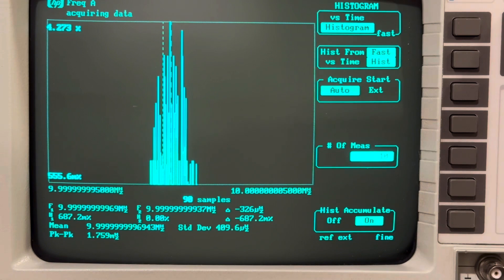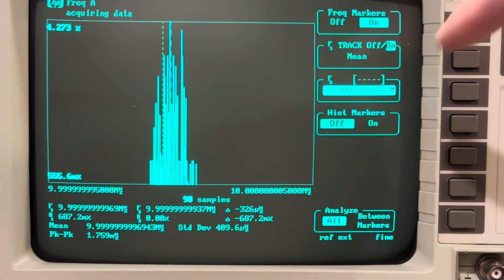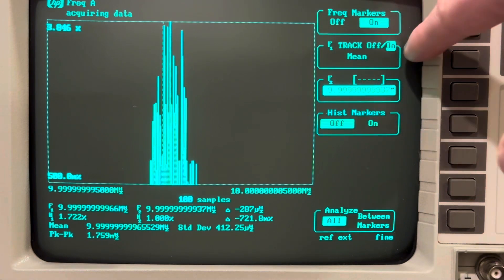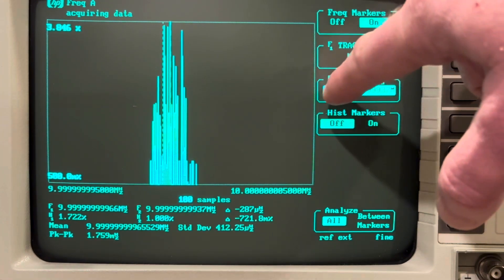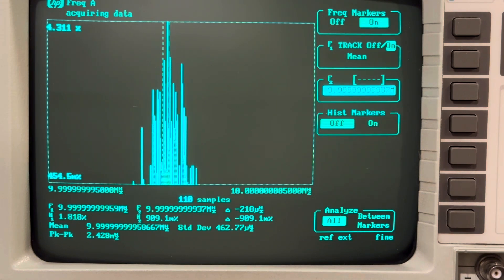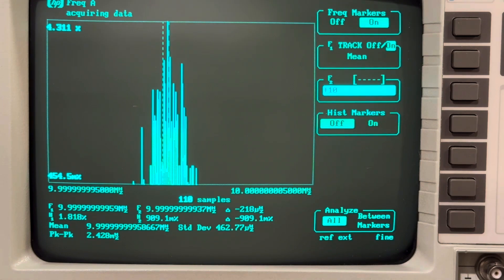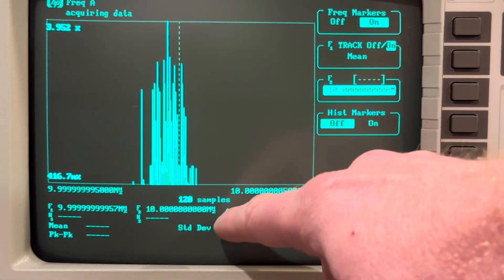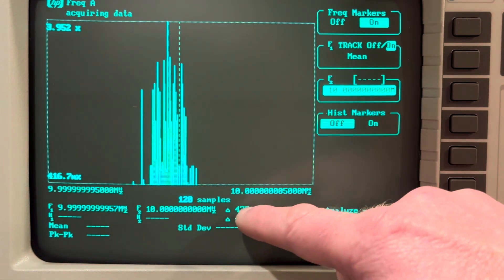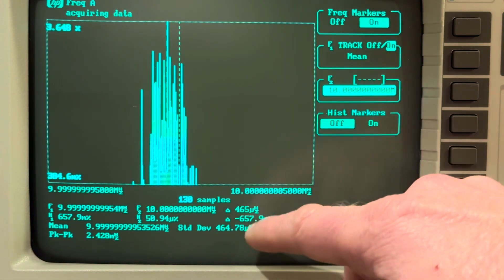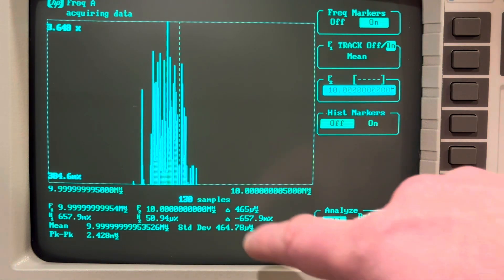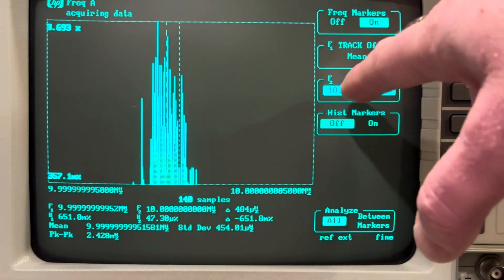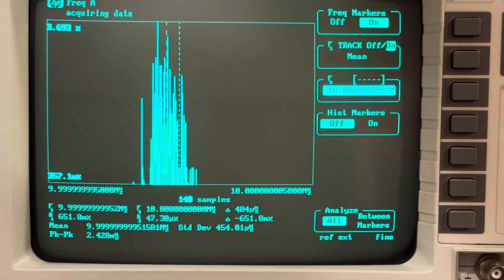Now if we go back over under verticals, see our markers. So over here, we can set up our tracking. So we're tracking on, and we're tracking compared F2, which we don't want, 0.9999. We want that 10 megahertz. So let's enter that 10 megahertz right there. So now it's going to show us a delta. And the delta right now is 433 microhertz. So the input signal average so far is 465 microhertz above my reference of F2, of 10 megahertz exactly.